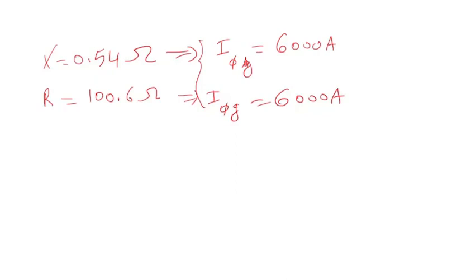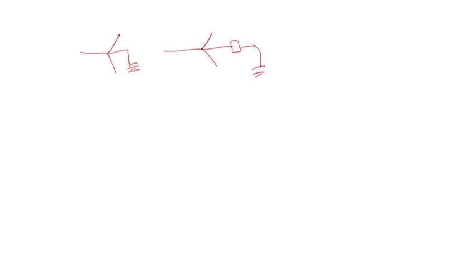That's because the system is mostly inductive, so the reactance dominates. When you add impedances — resistor plus j times X — since the reactive part is dominating, if you add a resistor you will need to add a large resistor to get the same result. Now, when we have the transformer, the high side is effectively solidly grounded, but on the low voltage side, any time you add an impedance — whether a reactor or a resistor — you can impact the effective grounding of the system.